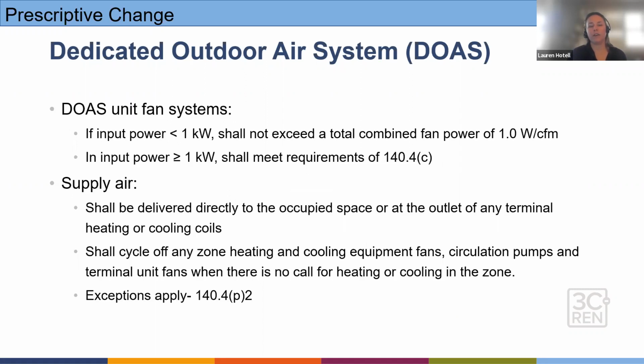And this also applies for certain climate zones. The exemption that I just mentioned for the economizers goes hand in hand with the DOAS system. If the input power is less than 1 kW, you cannot exceed a total combined fan power of 1 watt per CFM. If it's greater than 1, you need to meet the requirements in 140.4(c). Supply air needs to be delivered directly to the occupied space or at the outlet of any terminal of heating or cooling coils.